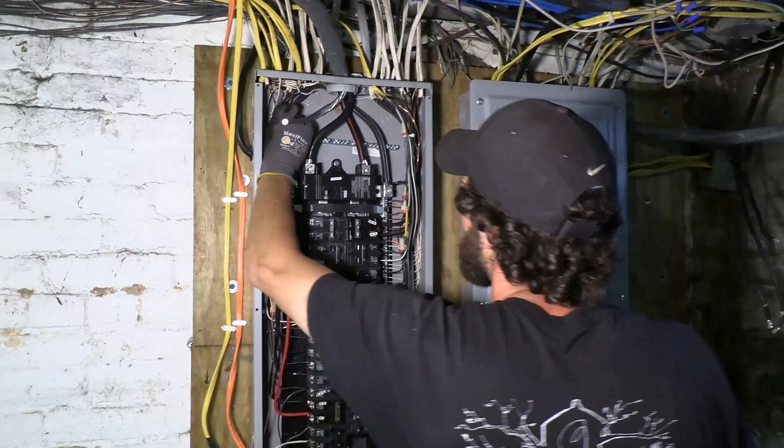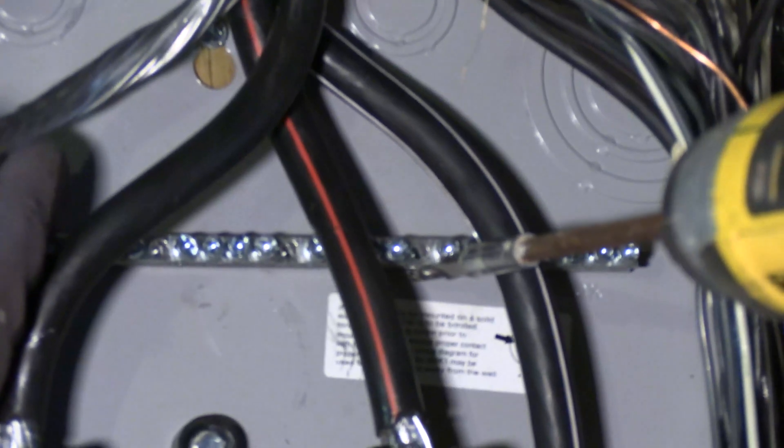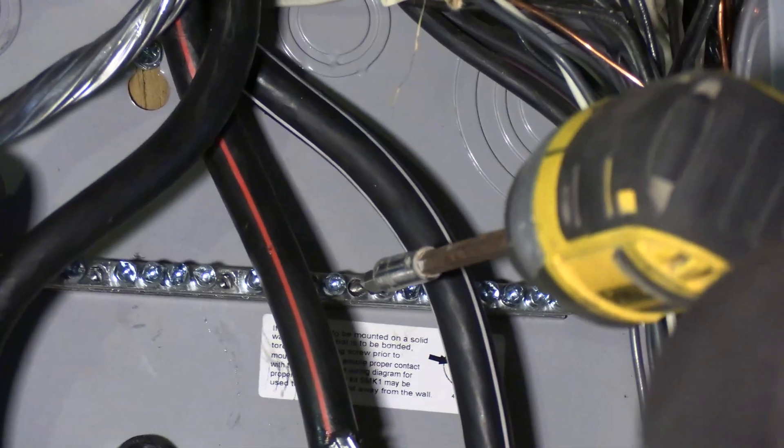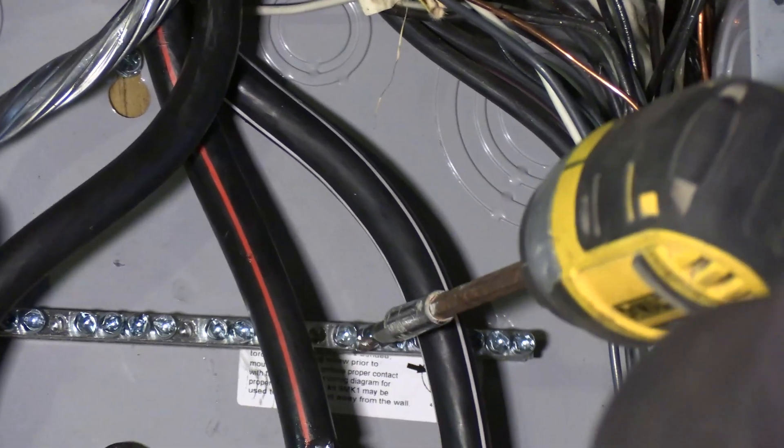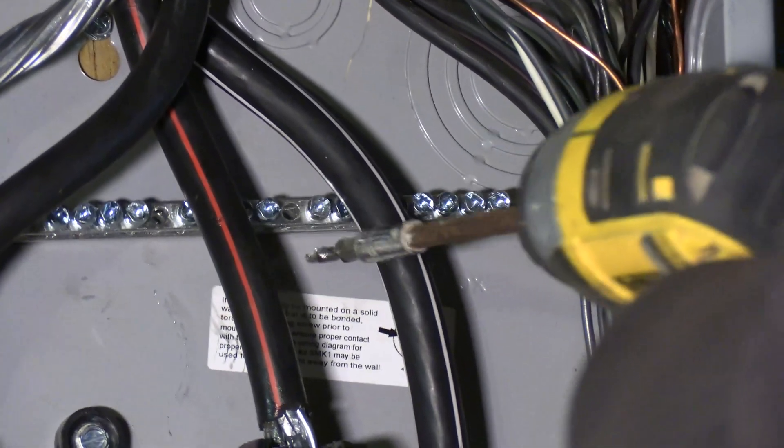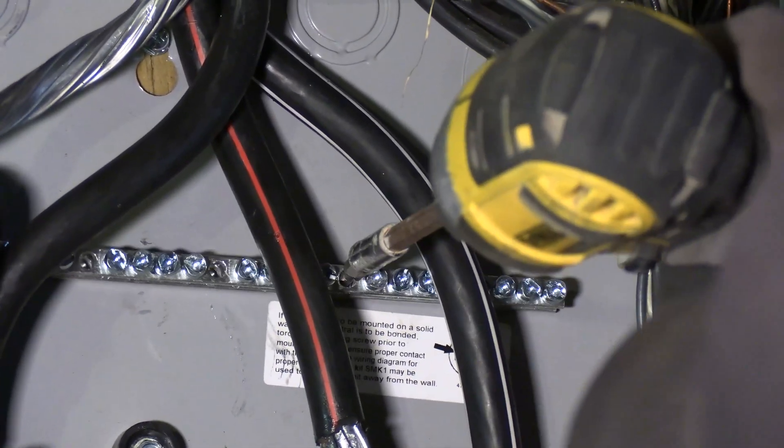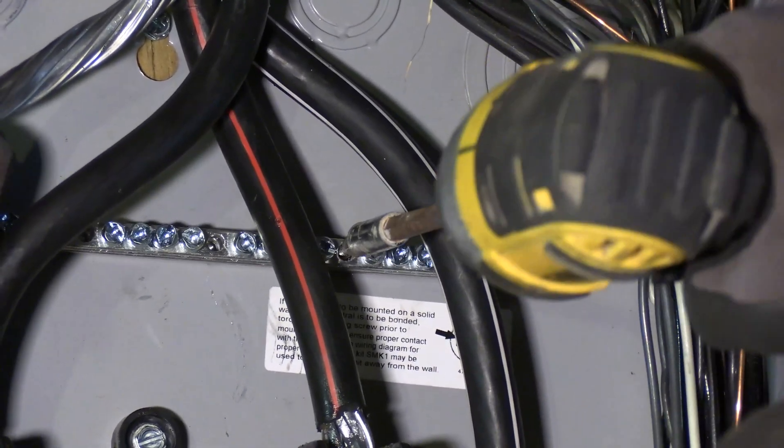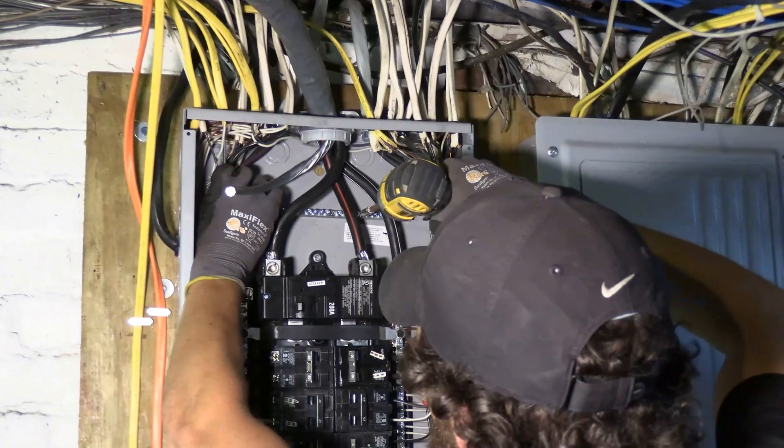It's pretty tight. There's not a lot of room to work. I want to make sure I'm not on that label. Most of my conductivity is going to be in the form of through the screws, but I don't want my ground bar to be on the label. Now this is an enamel surface. So there's not a lot there, but I want to get what I can. I want my ground terminal bar to be bonded, electrically bonded to my panel.